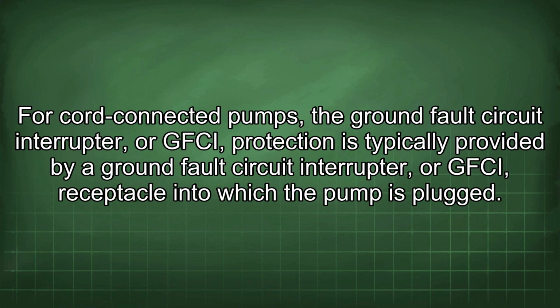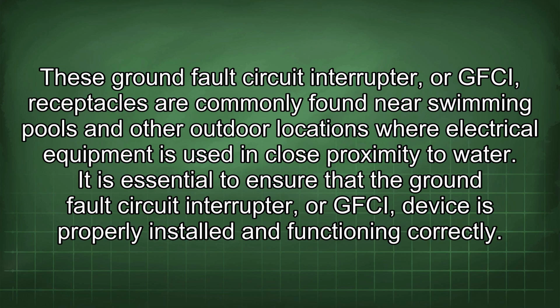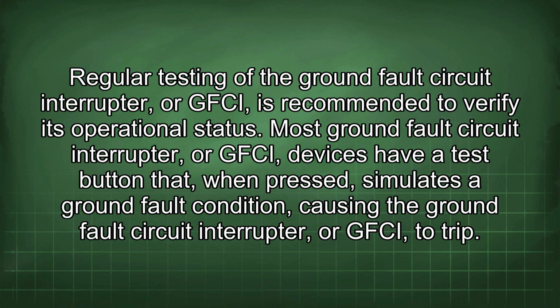For cord-connected pumps, the GFCI protection is typically provided by a GFCI receptacle into which the pump is plugged. These GFCI receptacles are commonly found near swimming pools and other outdoor locations where electrical equipment is used in close proximity to water. It is essential to ensure that the GFCI device is properly installed and functioning correctly. Regular testing of the GFCI is recommended to verify its operational status.